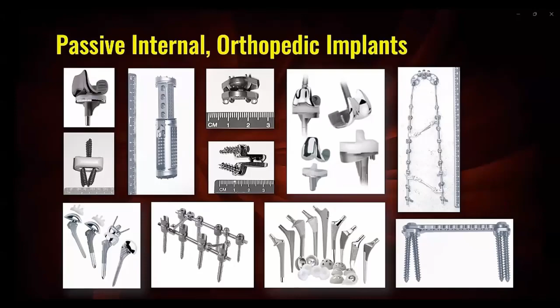Most orthopedic implants are made of weakly or non-ferromagnetic materials including commercially pure titanium, titanium alloy, cobalt-based alloys, tantalum, magnesium-based alloys, and austenitic or non-magnetic stainless steel. For orthopedic implants made of ferromagnetic material, in situ counterforces will be present that will prevent movement or dislodgement of the device in association with exposure to the static magnetic field of an MR system. While there is a theoretical risk of MRI-related heating of certain passive internal orthopedic implants, such as internal fixation systems used for the spine, to date, there has been no evidence of substantial heating occurring in a patient, nor a report of a patient burn associated with these implants related to the clinical use of MRI examinations.